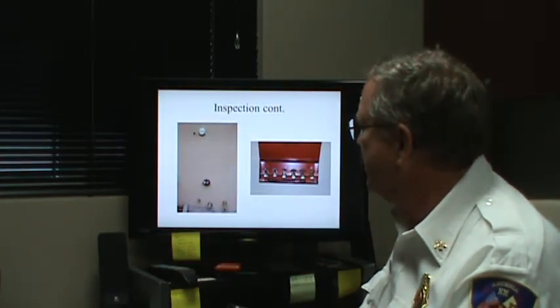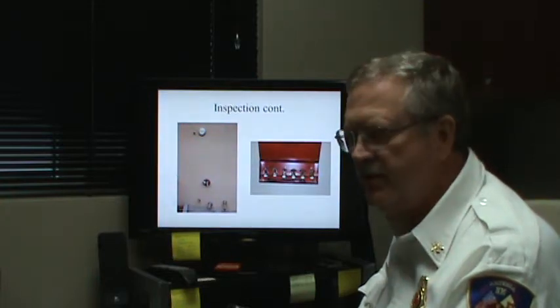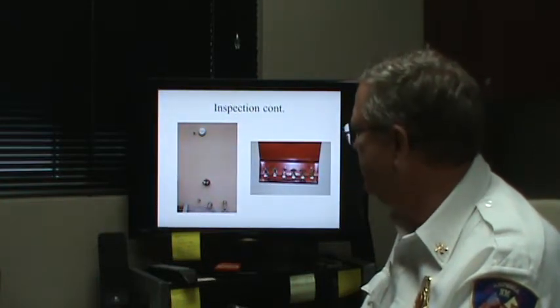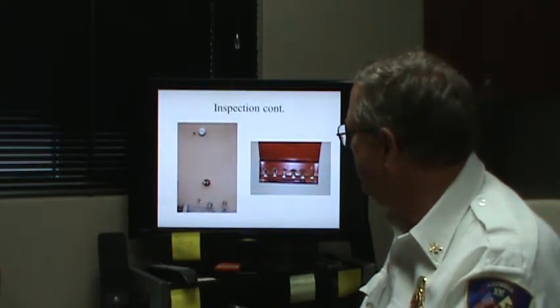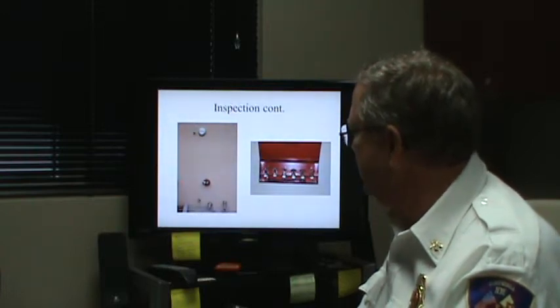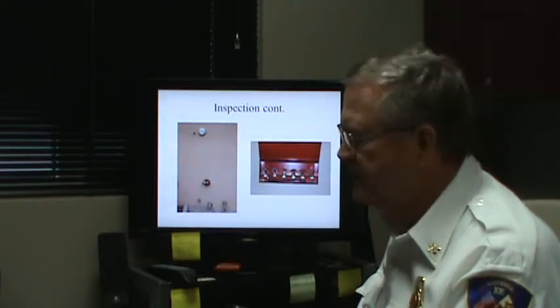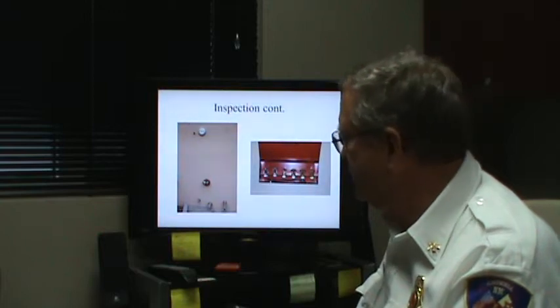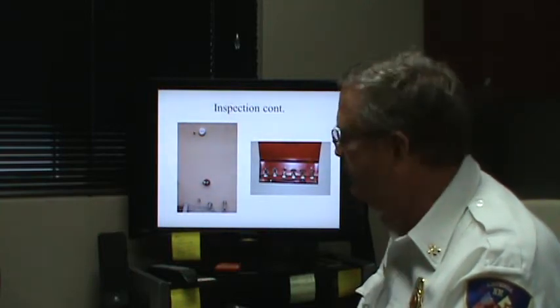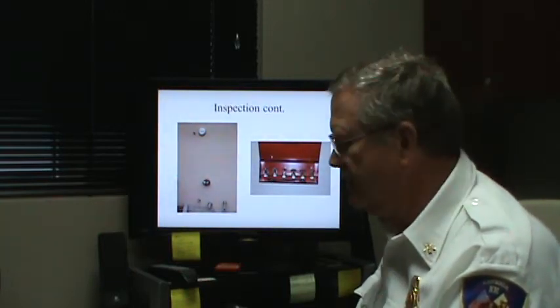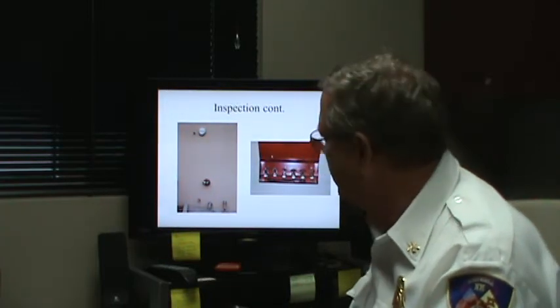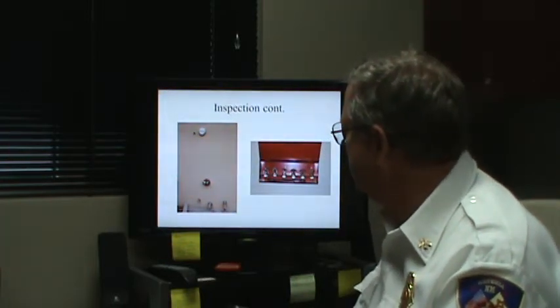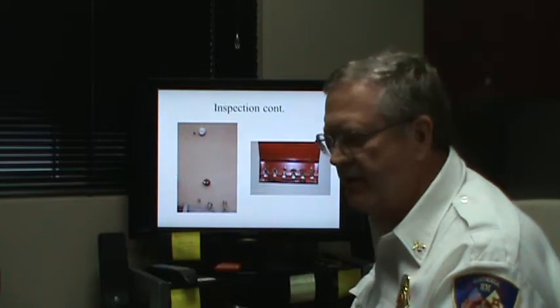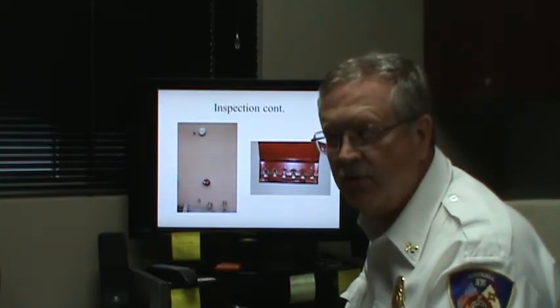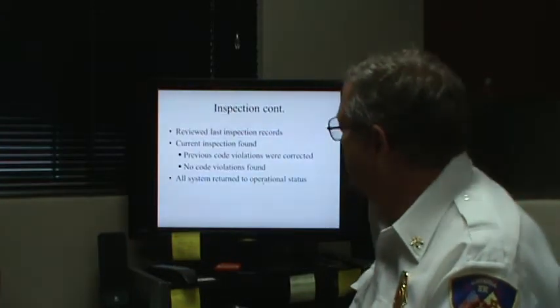Here is the gong outside and the water department hookup, and then there are the drains for the test that could be done. Here are the spare parts, the spare sprinkler heads, the wrench to take those off with, and then back behind this cover was another big socket. So all that was in good shape. Everything looked good. Everything's been tagged and recorded correctly.